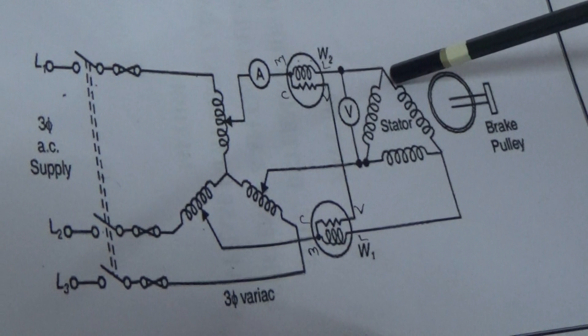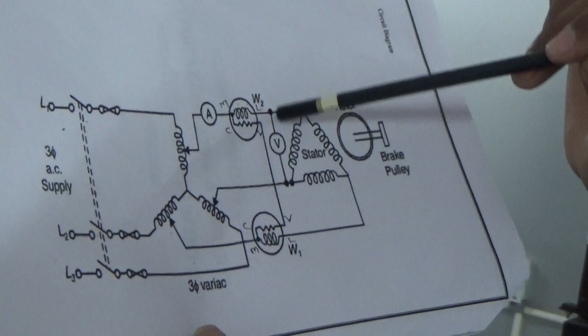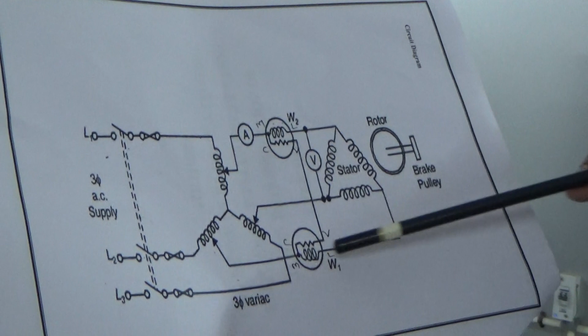One ammeter is connected in series with the first winding, or R phase, to calculate the line current. One voltmeter is connected across two phases to calculate the phase voltage. Two wattmeters are there, which will measure the actual power of the motor.